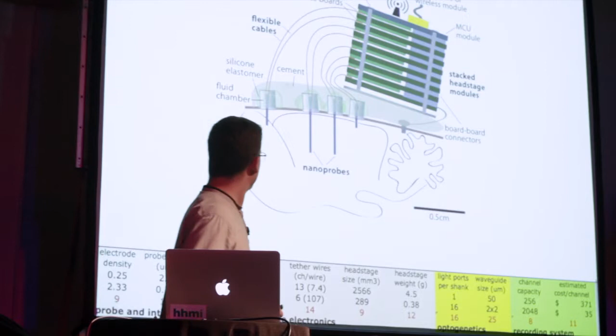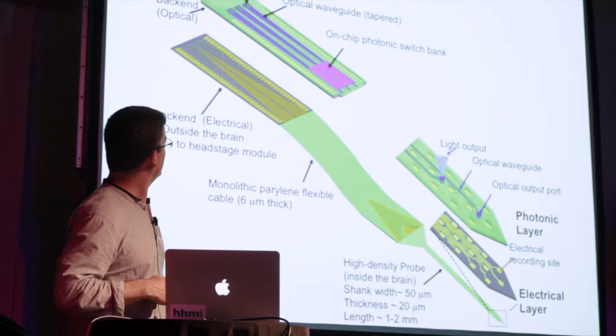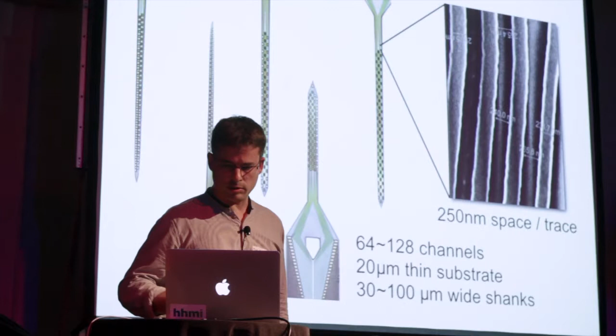First, the electrode technology. Just zooming in on one of these electrodes, it comprises a silicon electrode that's on the order of about half a human hair wide, about 25 microns thick, and has up to 128 channels on the electrode. Flexible interconnects, very small, very flexible cables about 6 microns thick, allow multiple electrodes to be placed in adjacent brain areas without putting tethering forces on the brain. And also, this is the interface to the recording electronics that also includes some optical stimulating components, which I probably won't have time to talk about today, but are in the works.